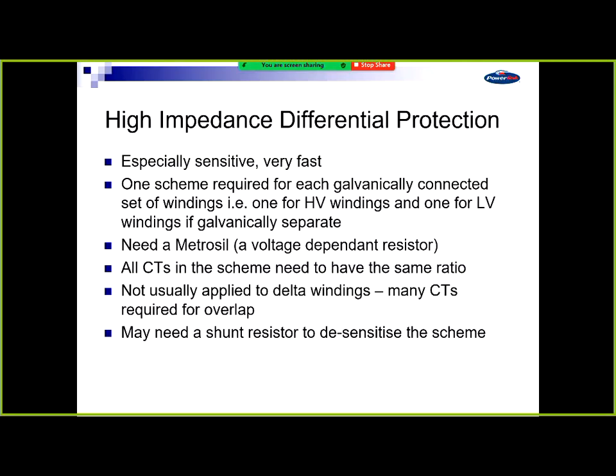You have one scheme for each galvanically connected set of windings. So if you've got an auto transformer, like where a lot of ours are, you have one lot of protection around the whole transformer because you've got one winding. If you've got an HV winding and an LV winding, you need two lots of bias differential, high impedance differential. You may need a Metrosil because the voltages can get really high, so it's really just a voltage dependent resistor. Problem with them is the CTs need to all have the same ratio. You can't have a different ratio on your CTs. They're not well suited to delta windings because it's a complex arrangement that you need to do to set them up to have the balanced currents. And because they're so sensitive, you may actually need a shunt resistor to desensitise them. So there have been times where we've said, that actually only needs a few amps of unbalance. We'd need to put a resistor in there to desensitise it.